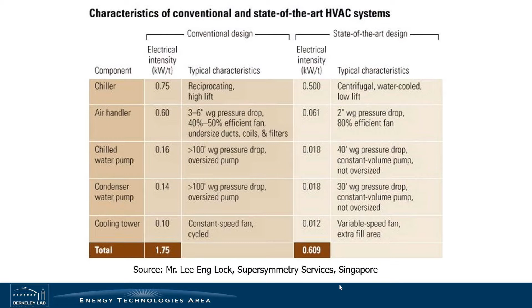For the air handling unit, this is the design of low pressure loss air duct and fan systems—you can drop from 0.6 all the way down to 0.06. Same thing for the chill water pump, condenser water pump, and cooling tower. The bottom line sums the total kilowatt per ton: conventional design is about 1.75, and state-of-the-art design can reach 0.6—almost a third of the conventional design. This has already been implemented in many real projects and buildings, through dedicated engineering enabling much more energy efficient HVAC systems, in this case the central chiller plant.